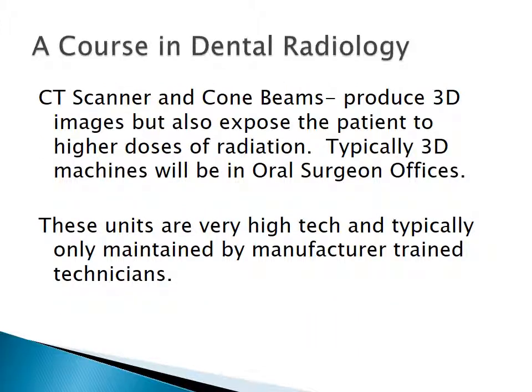When it comes to your CT or your cone beam systems out there, these guys will actually produce a 3D, very high quality image. However, they use, in some cases, 4 times the amount of radiation to get these images. So typically these 3D images are going to be in oral surgeon offices. These units are very high tech units, and typically the only people who are going to be authorized to work on these or get any kind of technical support on these are going to be manufacturer trained technicians.